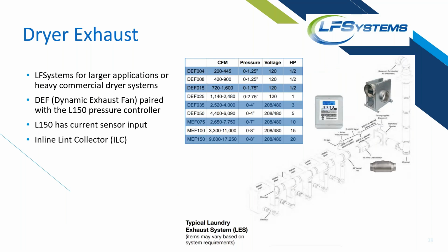With LFS systems, we can do anything from a small CFM, small laundromat or laundry system, all the way up to a large laundromat. And one of the cool things about this L150 controller is that we can actually have a current sensor input on it as well. So it can operate on pressure, but be activated as soon as that dryer turns on.